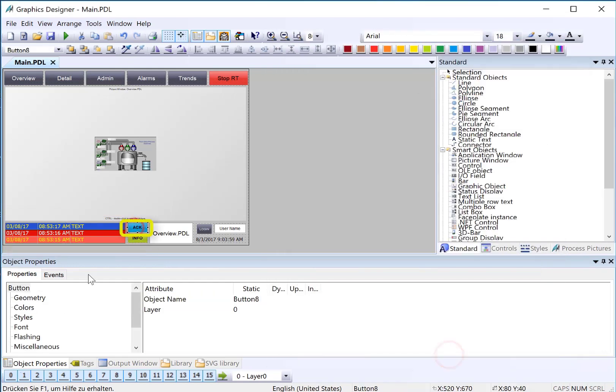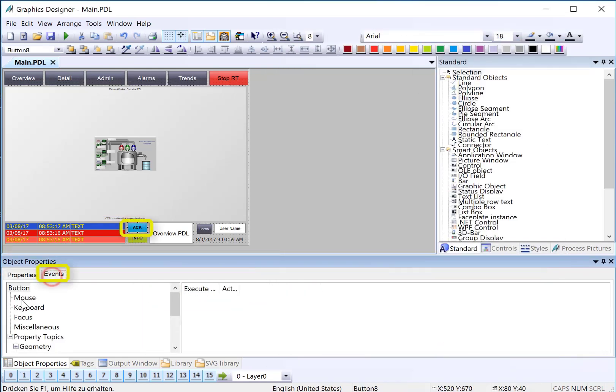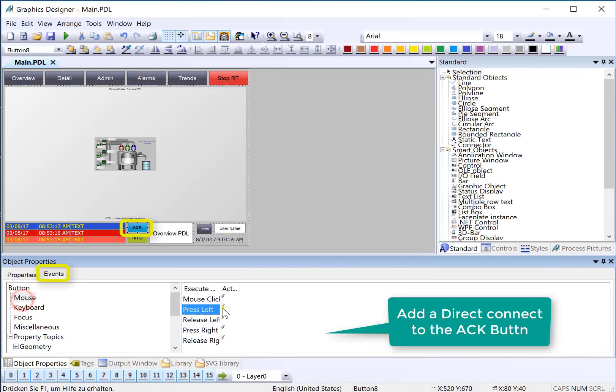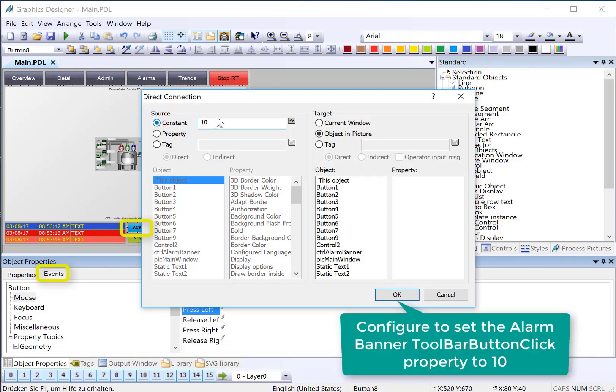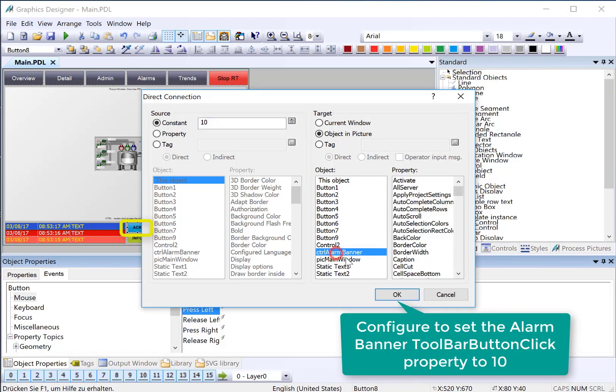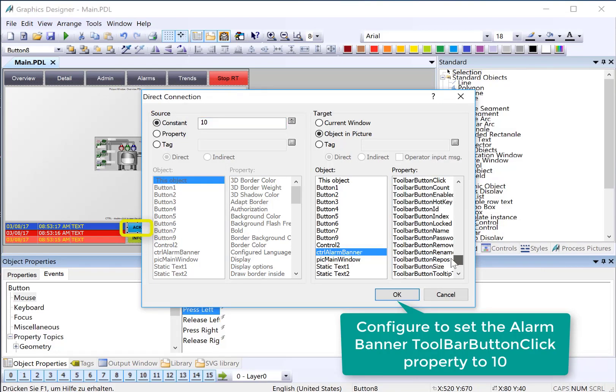We'll do the ack button first. We'll go to events and choose direct connect on our press left. We'll put the object ID in the constant. And then since we've named this well, it's easy to pick out our alarm banner. And there is a property called toolbar button click.